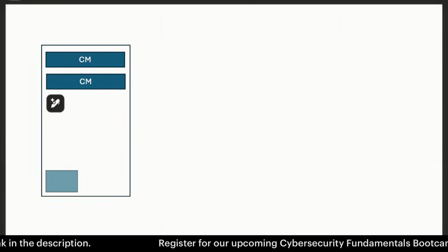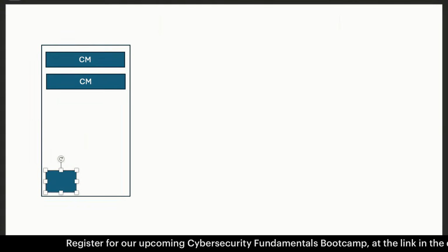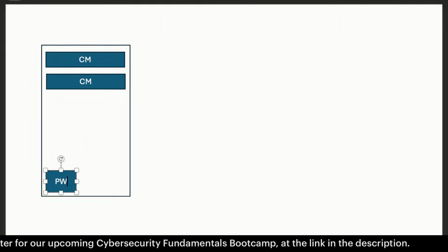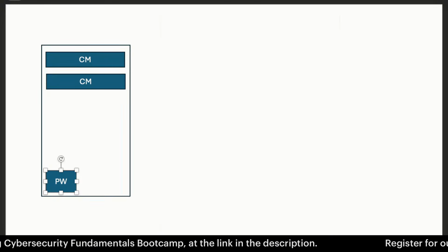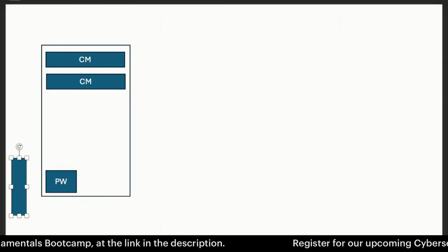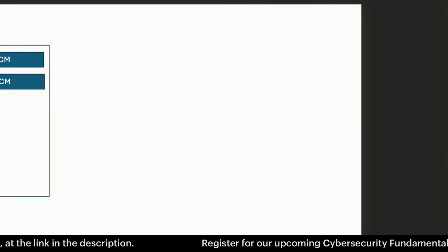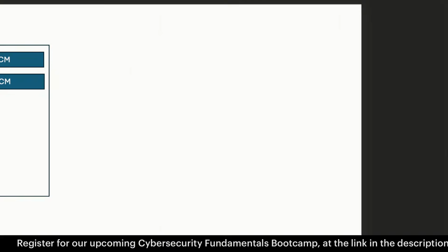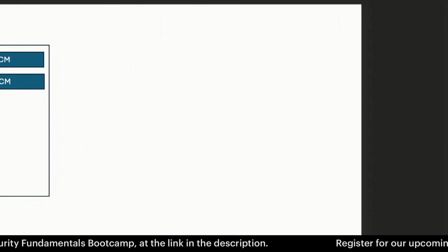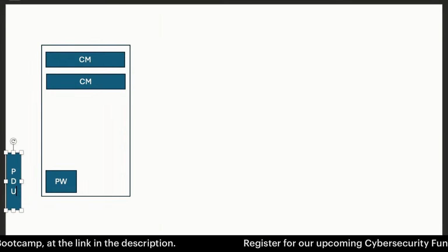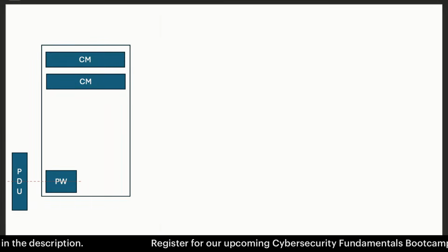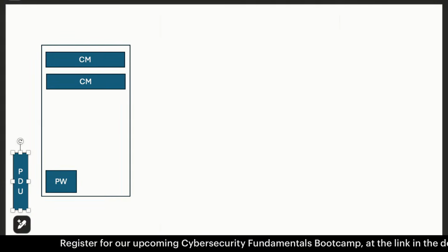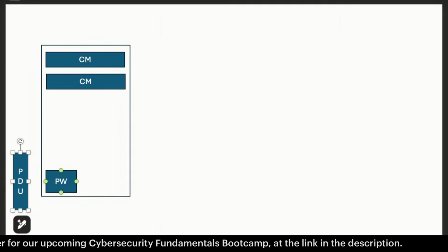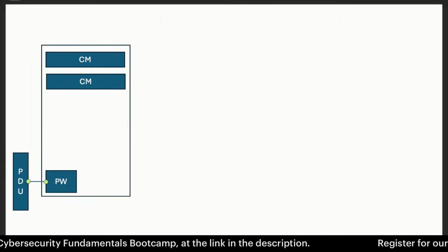Now we've got this $100,000 router, easy, and this is the power supply. And we plug this power supply into something called a PDU, or a power distribution unit. These PDUs themselves typically support about 6,000 watts on average, 30 amps, let's say 240 volts, about 6,000 watts when all is said and done, a little more than that. So this goes into the PDU, and the PDU plugs into a single outlet, and the PDU has a circuit breaker.